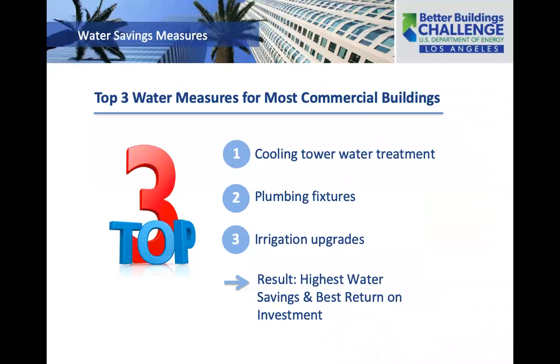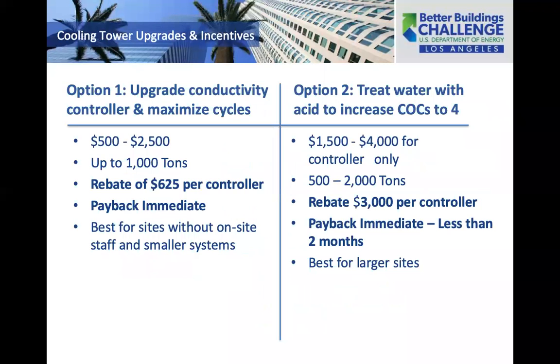And making sense, the top 3 measures with the highest water savings and best return on investment, directly correlating to the top uses, are cooling tower water treatment upgrades, installing high efficiency plumbing fixtures, and upgrading your irrigation system. It's really as simple as that. Every property will be slightly different, but for 80% of the commercial properties in Los Angeles, these will be the top 3 measures. So what are your options for cooling towers?